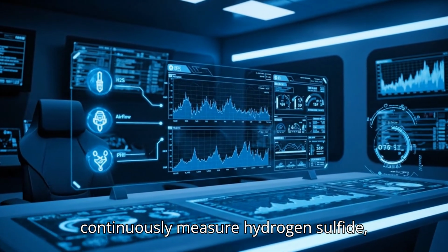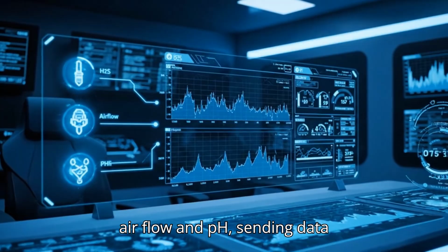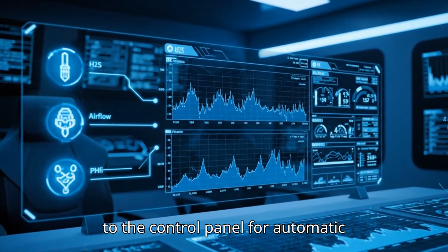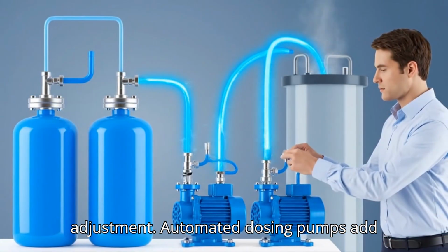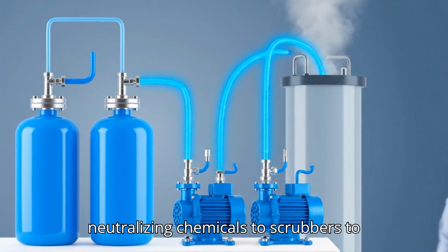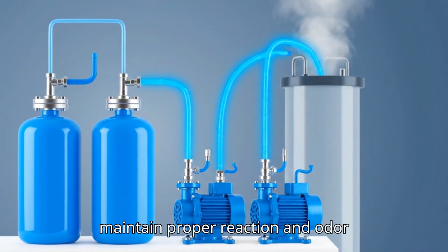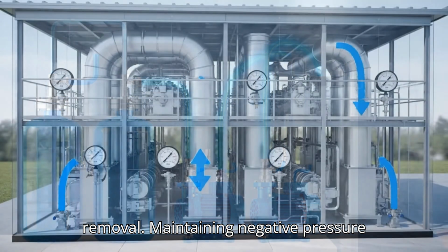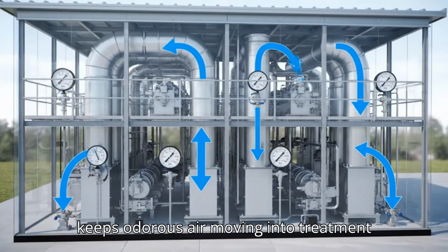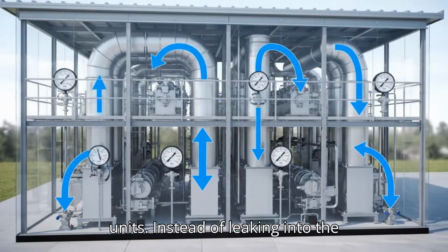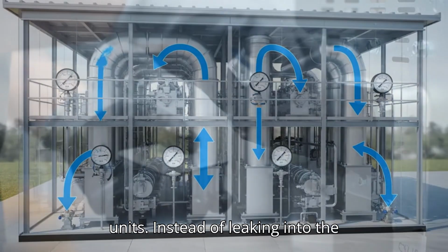Sensors continuously measure hydrogen sulfide, airflow, and pH, sending data to the control panel for automatic adjustment. Automated dosing pumps add neutralizing chemicals to scrubbers to maintain proper reaction and odor removal. Maintaining negative pressure keeps odorous air moving into treatment units instead of leaking into the environment.